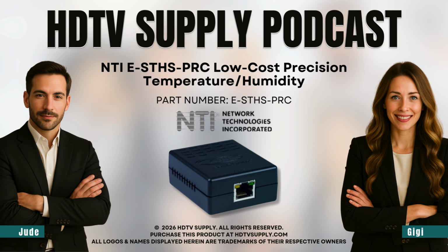So what does that mean in simple terms? Instead of sending a signal on one wire and comparing it to ground, which is really susceptible to electrical noise, like from power cables or motors, RS-485 uses two wires, and the receiver just measures the difference in voltage between those two wires. So any noise that hits both wires at the same time just gets canceled out. This makes the digital signal incredibly robust, so the precision reading from the sensor arrives intact, even at 1,000 feet.